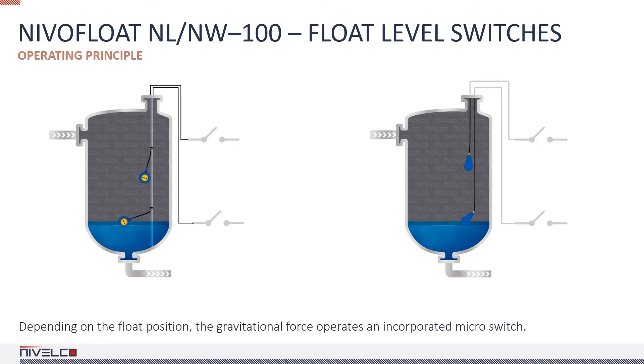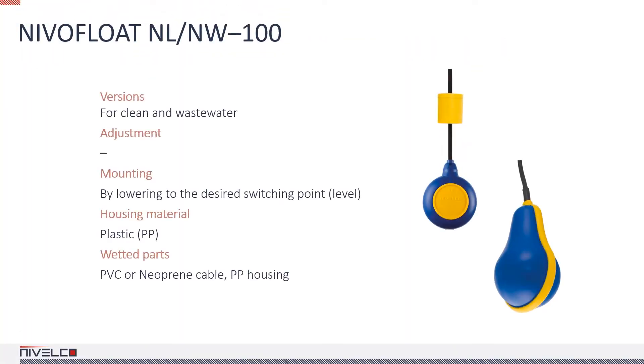The NivoFloat is suitable for various control tasks such as liquid level monitoring and pump control. The float for pure water applications can be attached to a rigid support frame or simply hung. In the former case, the switching level can be adjusted by changing the length of the cable between the mounting point and the float housing. In the second case, the same can be adjusted by changing the position of the counterweight.